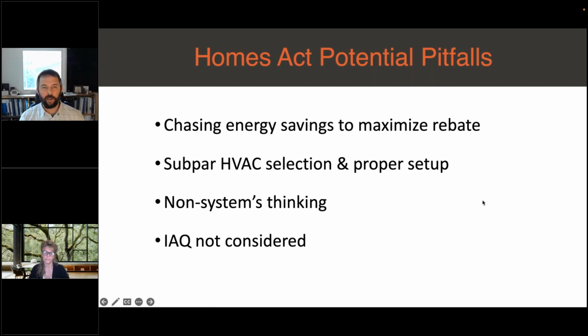The modeling software that will likely be used really only looks at sensible BTUs in the calculations. It does take latent BTUs into account, but not as strongly, so savings are weighted more on sensible. Because of this, supplemental dehumidification is typically a big energy penalty, because even though it may be required to maintain interior humidity, it's viewed as an energy user with no benefit in these modeling softwares.